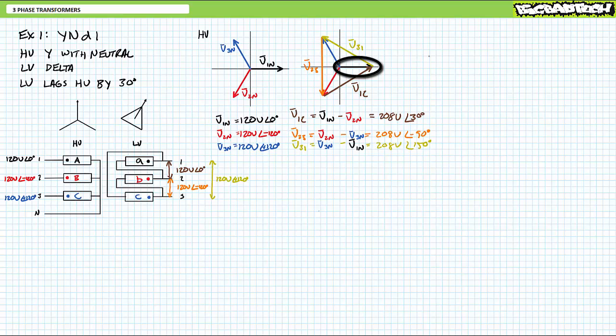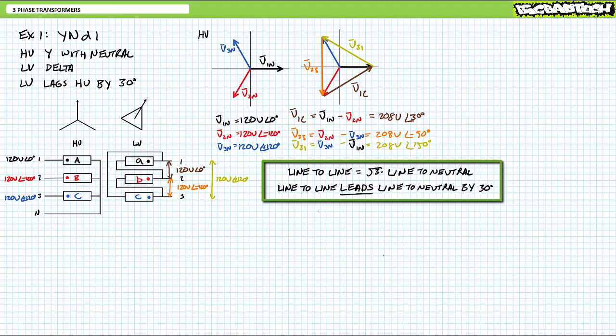The phasor diagram clearly illustrates the reference line-to-neutral voltage arrow. The line-to-line voltages are square root three — roughly 1.73 times — the line-to-neutral voltages, and still exhibit a relative phase shift of 120 degrees between each other. Additionally, the line-to-line voltages lead the nearest line-to-neutral voltages by 30 degrees. Make note of this fact, because we're going to be using it in reverse on the low voltage side.